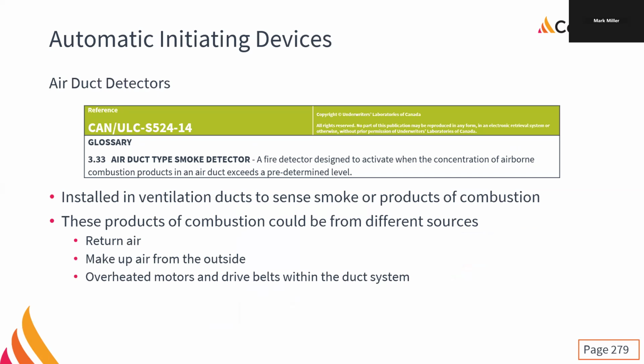Take a giant leap back in technology. Air duct detectors. We call them duct smokes, right? Because they go in the ductwork and they're smokes. Right? And we use them to sense the smoke, the products of combustion inside the ductwork.